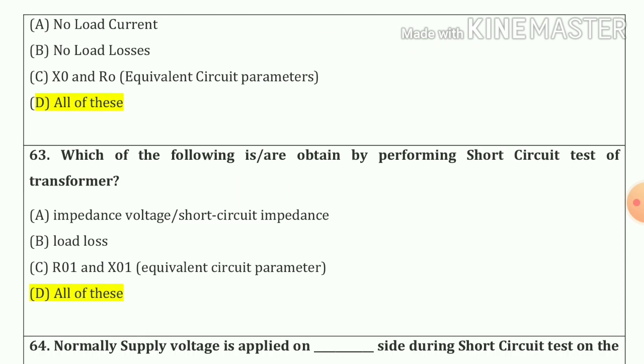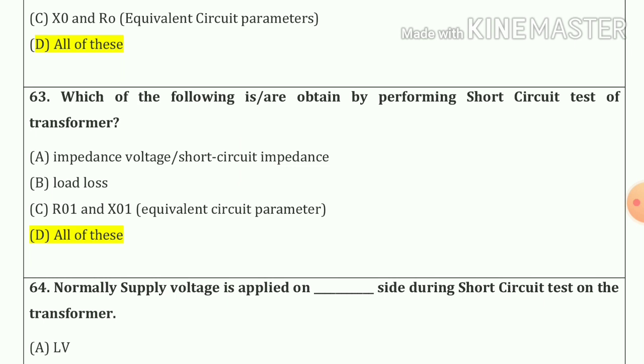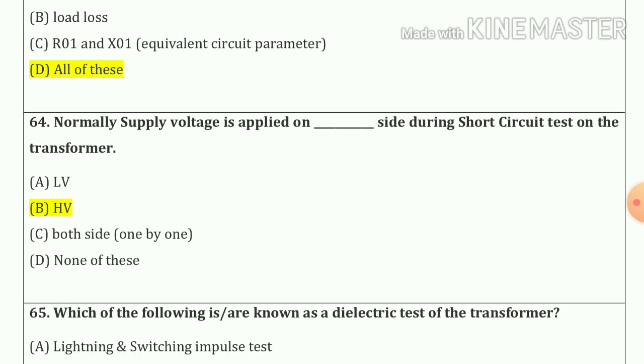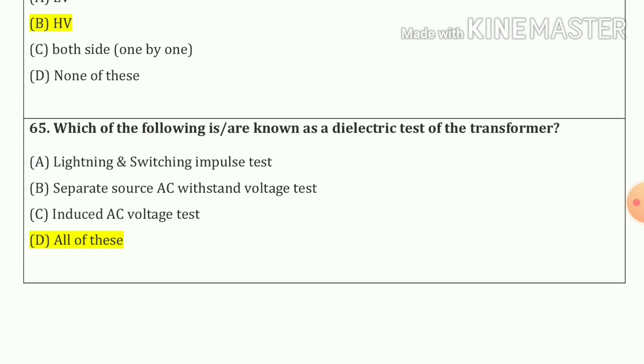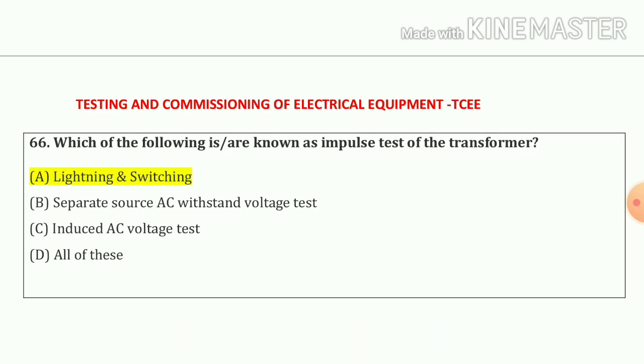Now question number 63. Which of the following are obtained by performing short circuit test of transformer? So our answer is option number A, impedance voltage or short circuit impedance, load losses, R01 and X01 equivalent circuit parameters. So our answer is all of these. Now question number 64. Normally supply voltage is applied on HV side during short circuit test on transformer. So our answer is high voltage, otherwise we can say as a HV side. Now question number 65. Which of the followings are known as dielectric test of transformer? So our answer is option number A, B and C also. So our answer is all of these. Question number 66. Which of the following tests are known as impulse test of transformer? So our answer is option number A, lightning and switching.